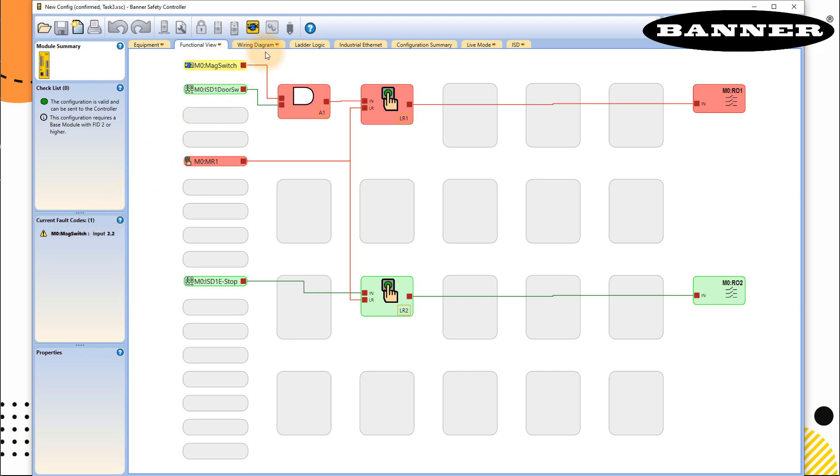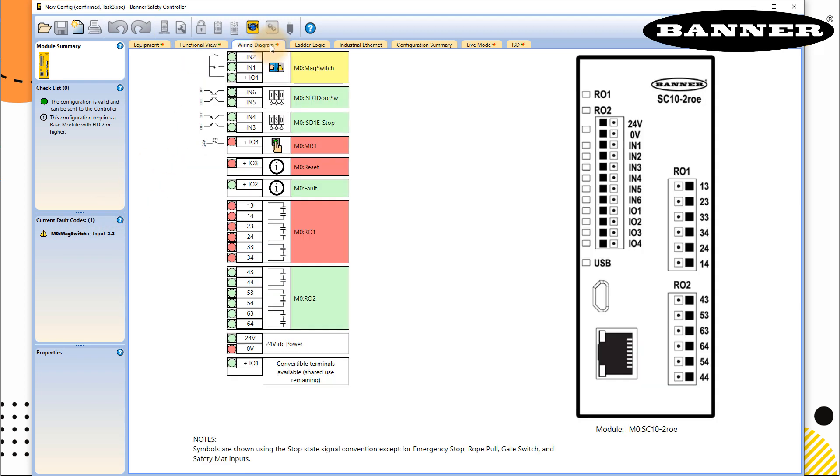Okay, you can maybe also see that here, magnetic switch is not connected properly. And this fault is detected because IN1 and IN2 both are true. And if both of the signals are true, which means the sensor is not perfectly aligned. And that's the best way to determine the fault in the software.